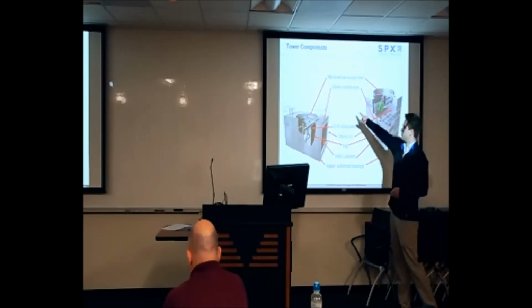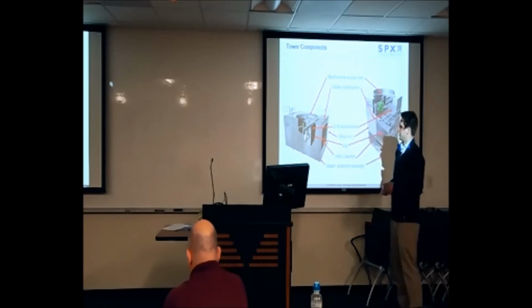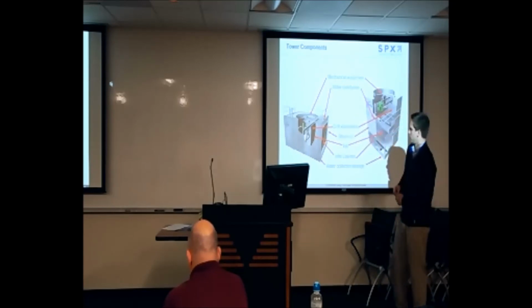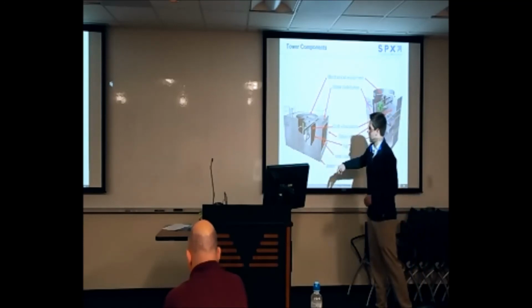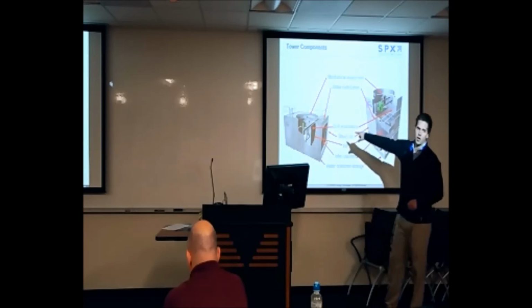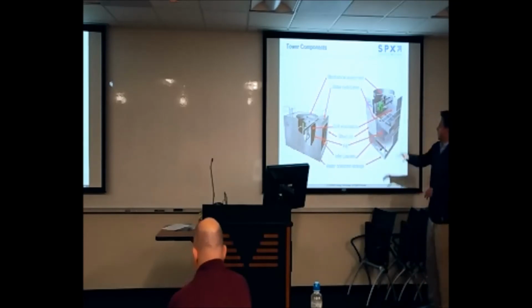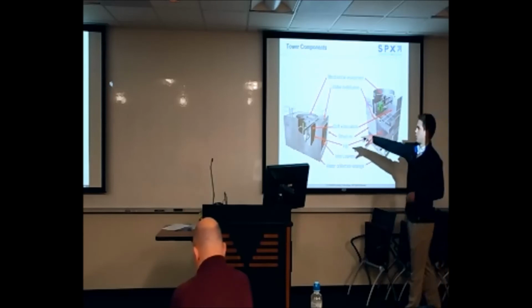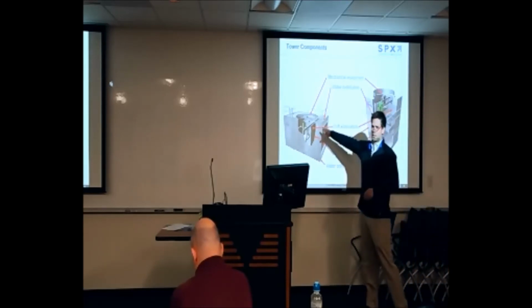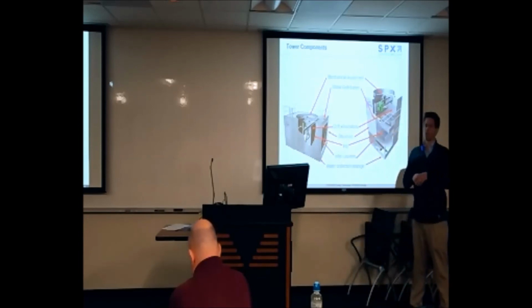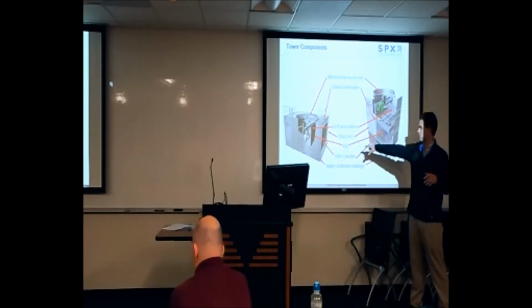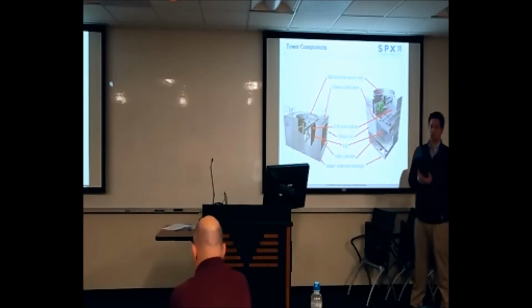You also have your water distribution up here, and this can either be with HC valves for direct inlet, or we can pipe from the bottom of the tower or the side of the tower and have internal piping that will dump into your water distribution basins. Once the water gets in those distribution basins, we have an array of nozzles in what we call the hot water basin. The purpose of the nozzles is to properly distribute the water across the fill media, which I'll discuss in just a second. The good thing about crossflow is you have gravity-fed basins, which means that your pumps only require to get the water up into those basins. From there, gravity and the size of the nozzles that we select for your tower will properly distribute it amongst the fill.